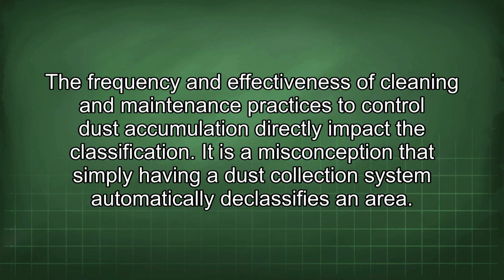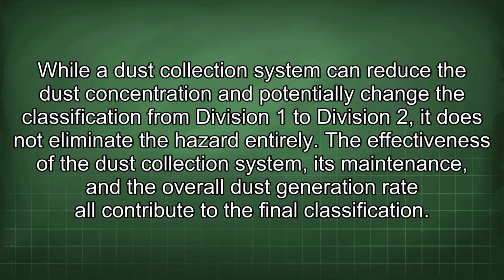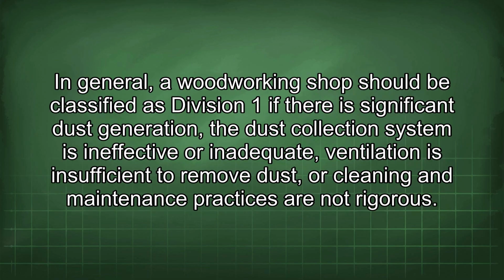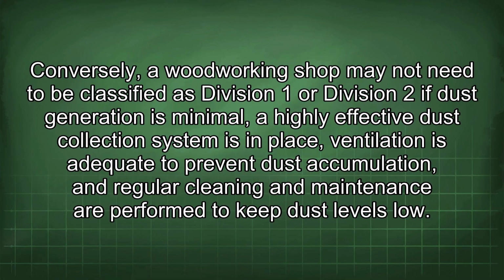It is a misconception that simply having a dust collection system automatically declassifies an area. While a dust collection system can reduce the dust concentration and potentially change the classification from Division 1 to Division 2, it does not eliminate the hazard entirely. The effectiveness of the dust collection system, its maintenance, and the overall dust generation rate all contribute to the final classification. In general, a woodworking shop should be classified as Division 1 if there is significant dust generation, the dust collection system is ineffective or inadequate, ventilation is insufficient to remove dust, or cleaning and maintenance practices are not rigorous. Conversely, a woodworking shop may not need to be classified as Division 1 or Division 2 if dust generation is minimal, a highly effective dust collection system is in place, ventilation is adequate to prevent dust accumulation, and regular cleaning and maintenance are performed to keep dust levels low.